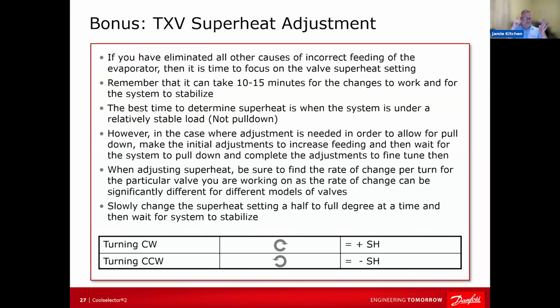Keep a note on the amount that you change it, the values, and the time. Because let's say you're decreasing superheat and the valve was stuck, and suddenly you've lowered the superheat enough that boom, whatever was causing the valve to stick flies open. And it wasn't a superheat issue. It was a valve stuck. Now you've got to go back and put it to where it was, right? So if you know the number of turns you did, it's great. But if you don't, it can be a bit of a struggle.